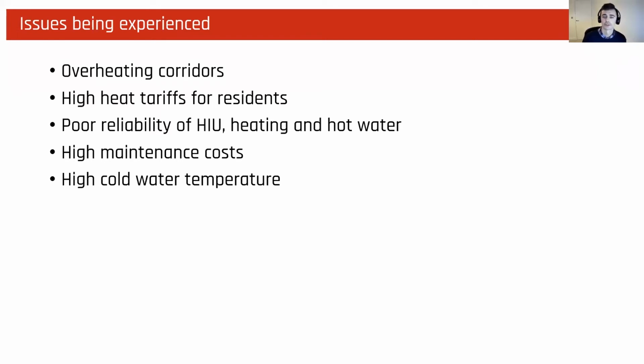And then moving on to the maintenance costs, this is actually related to the poor reliability of the HIU. There were a lot of call outs required on site and repairs, which again added to the residents' perception of the system being poor. Another point to note here is that there were very high heat losses from the pipework, which was actually impacting the cold water temperatures on site, which were seen to be above 25 degrees in some instances.